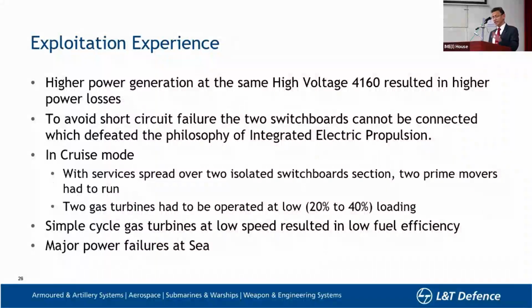Despite all these investments, the DDG 1000 destroyers also could not come up to expectations. The power generation of 78 megawatts at a medium voltage of 4160 volts resulted in higher power losses. Compare this to the Type 45, which also had 4000 volts but only 47 megawatts - these people went for 78 megawatts still at 4000 volts. They could have gone for 11 kV, but as a result, the power losses were much higher.